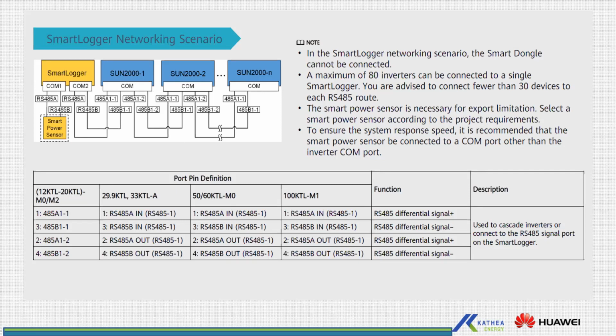All HUAWEI devices use standard communication, so your RS485 A equals A, B equals B. They do not support inverted communication. So from the logger to all the inverters, your A equals A, whether on in or out, and B equals B. And then if you have a meter, you wire your meter A and B to the other COM port.